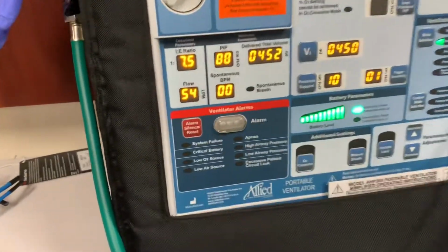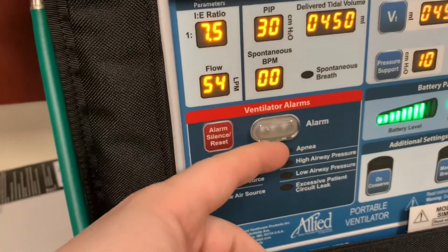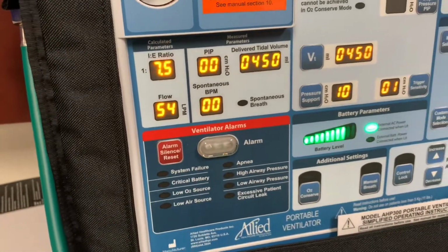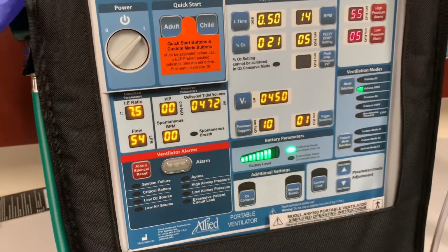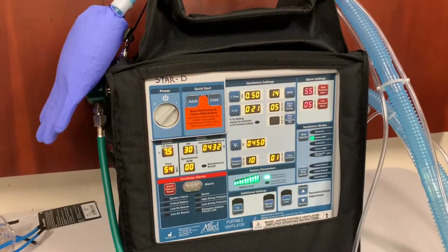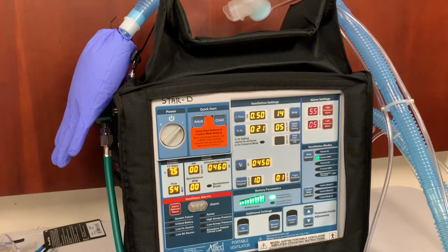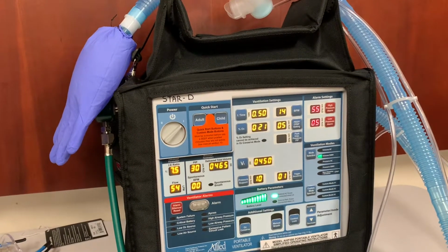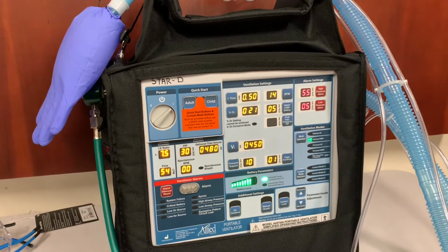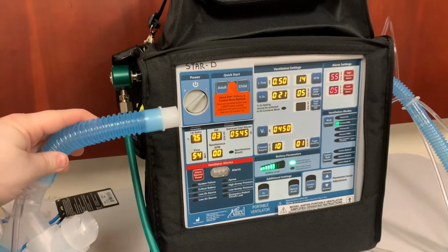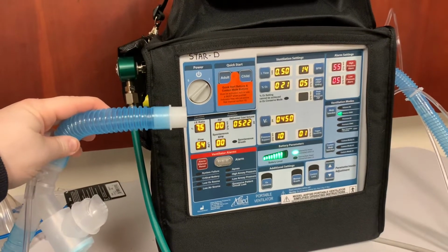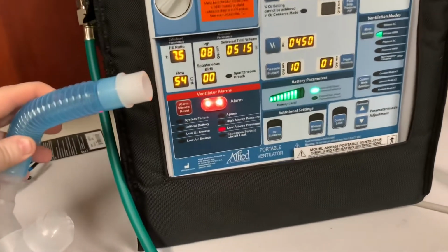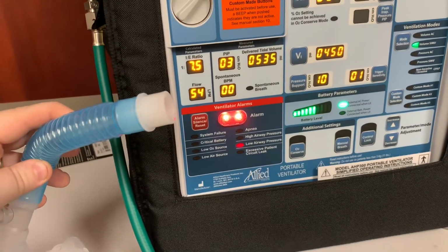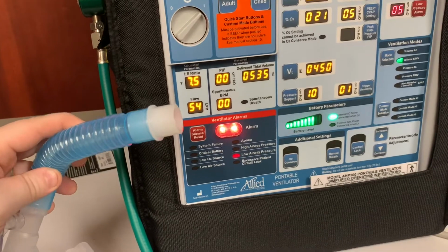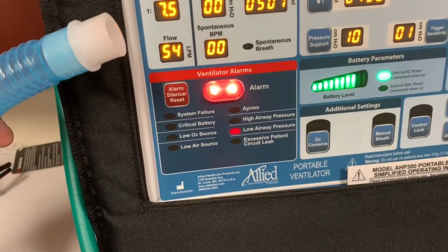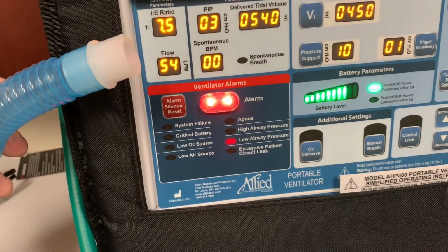When it comes to alarms, there are 2 types on the AHP 300. First, the alarm that has a big protruding light right here that will beep and will light up red when there currently is a problem ventilating that's requiring you to address it. We're going to demonstrate the alarm now by disconnecting the glove, which will simulate having a disconnect in your circuit from the intubation tube. Now that we have the glove disconnected, you can see that it is alarming, and it will continue to beep. It also is showing you what is the particular issue, in this case, low airway pressure.